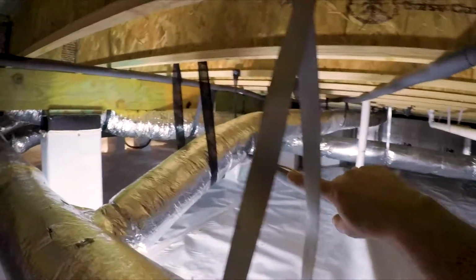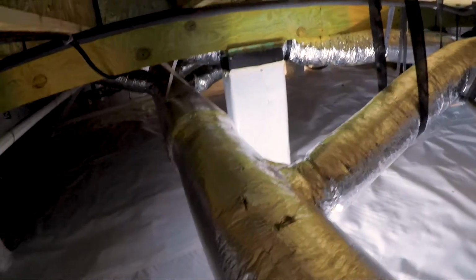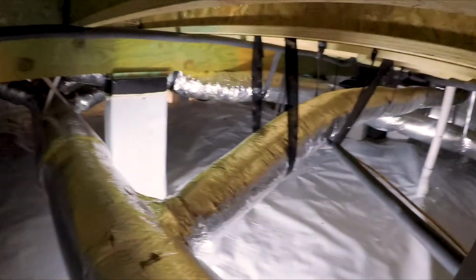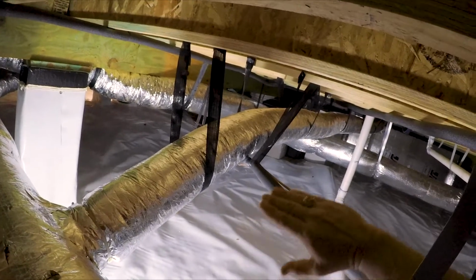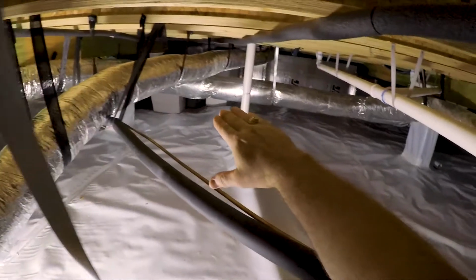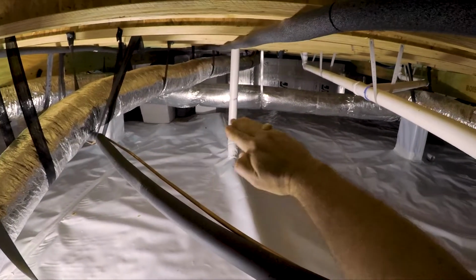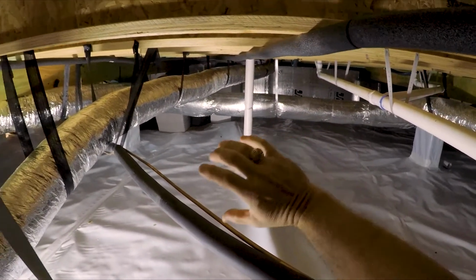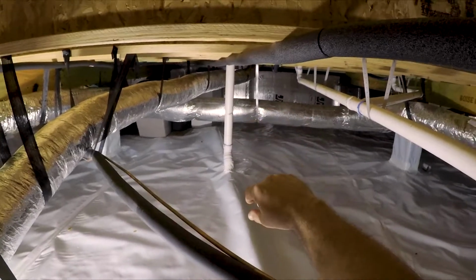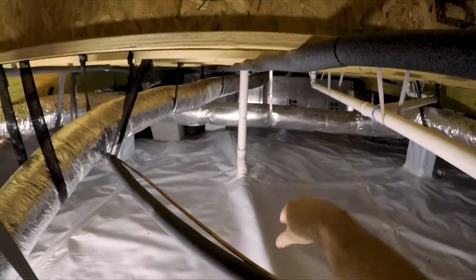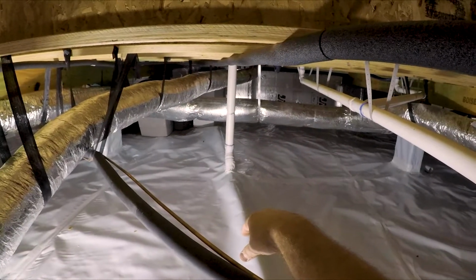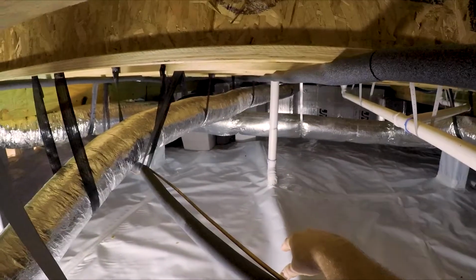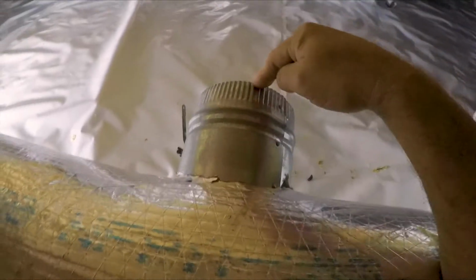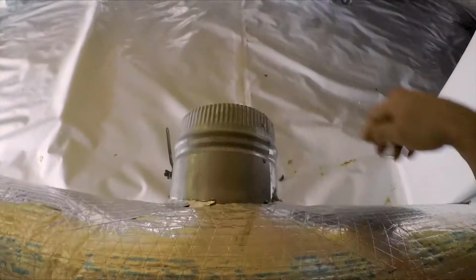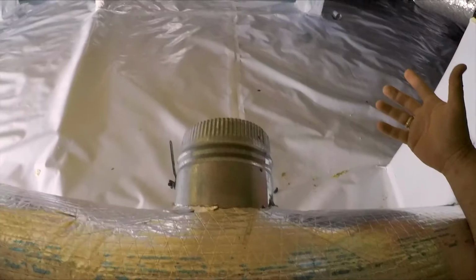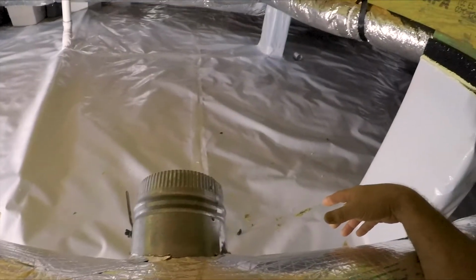So a few things to point out. The flex duct runs, you'll see they're running off of a trunk line here. This trunk line branches off, and the flex duct is very well supported. So all of the flex ducts run nice and flat and smooth. They're pulled taut, and no dips or curves, sharp bends in the flex duct. That reduces the airflow. Right here is one of the supply ducts blowing air out into the crawl space, maintaining humidity and maintaining temperature in the crawl space.